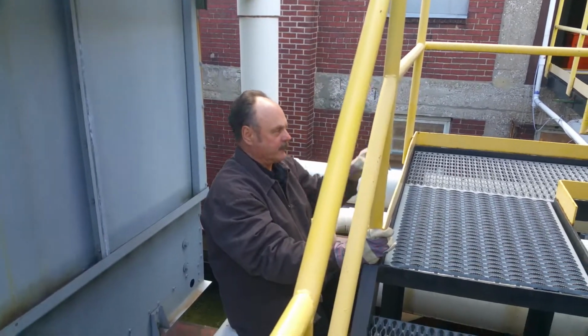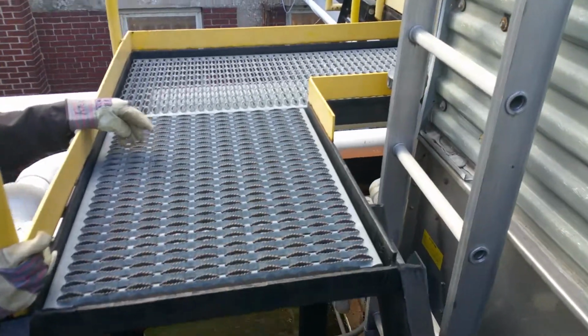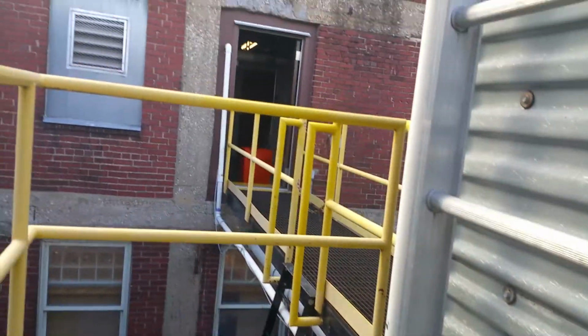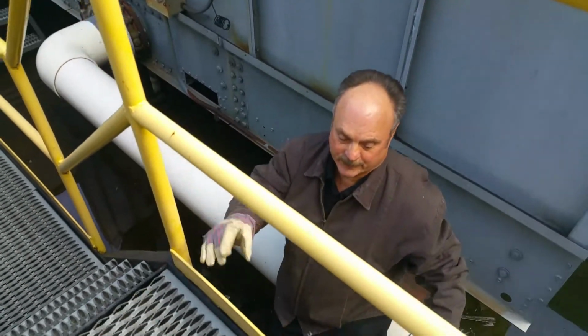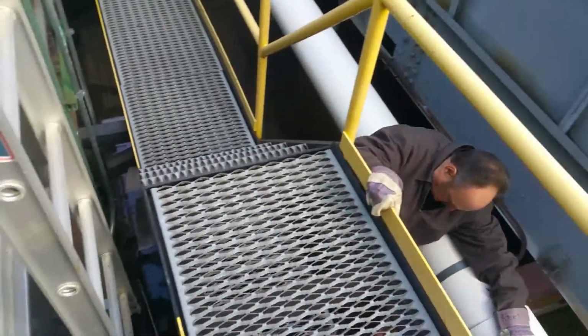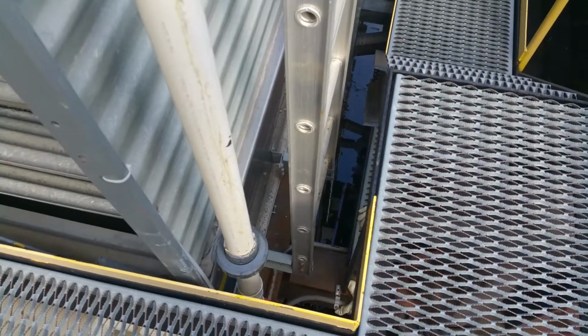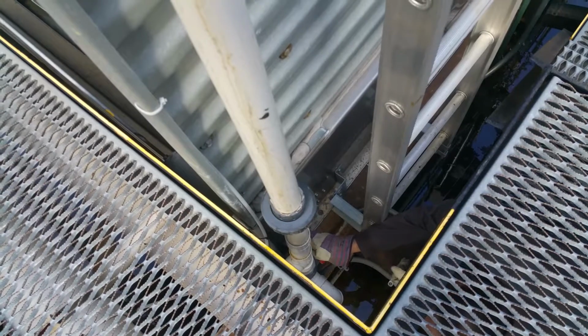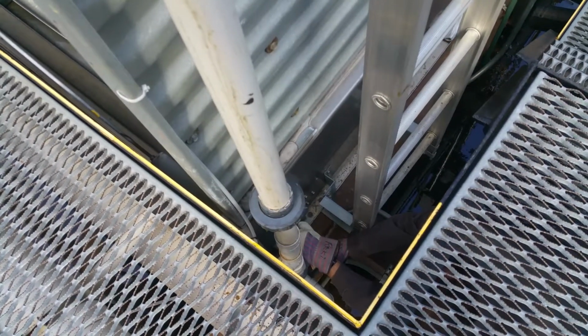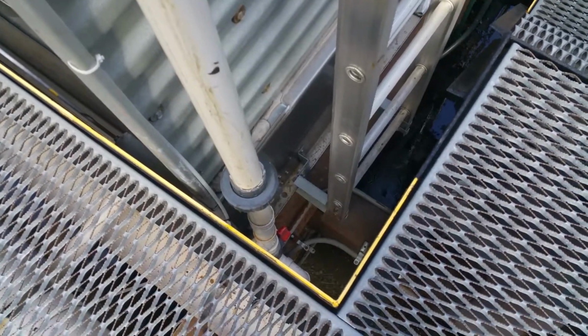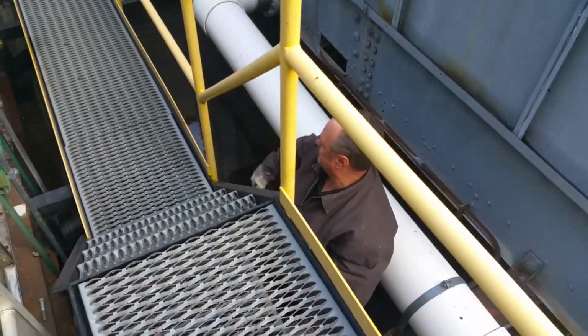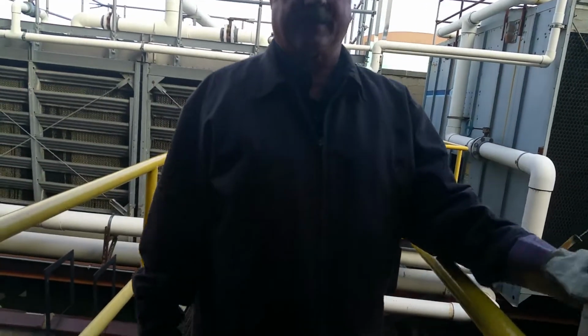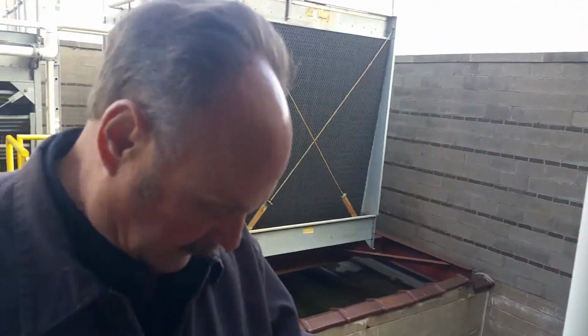Right. So we're draining this valve here. This line goes to the top of the cooling tower because that comes from the south locker room pump located on the 4th floor. So we have to drain this so the pipes don't freeze and break during the winter months. So that's what we're doing. So we have to drain this line also, because that comes from the condenser water pump for the south locker room, so we got to open this. There's a drain plug at the bottom of it. We got to open it to prevent this from freezing and breaking during winter months.